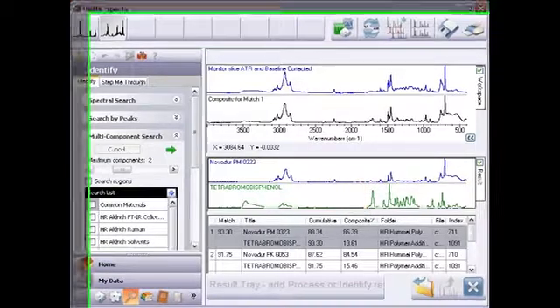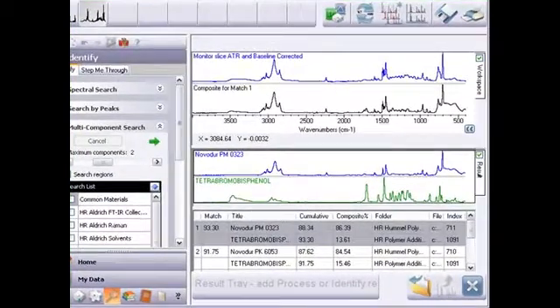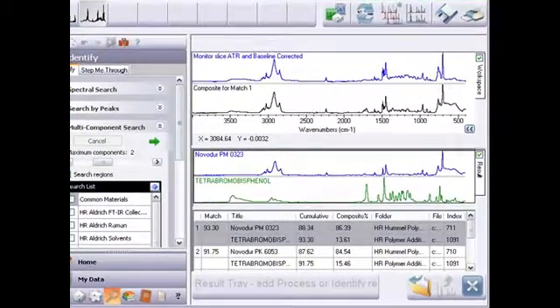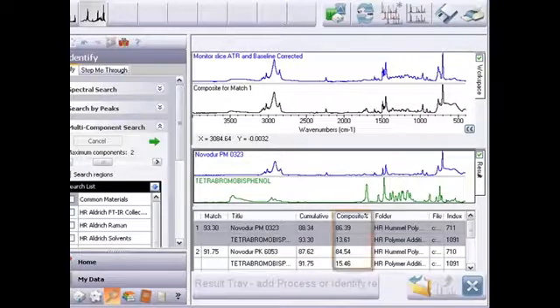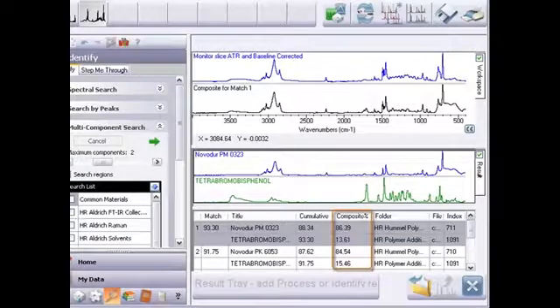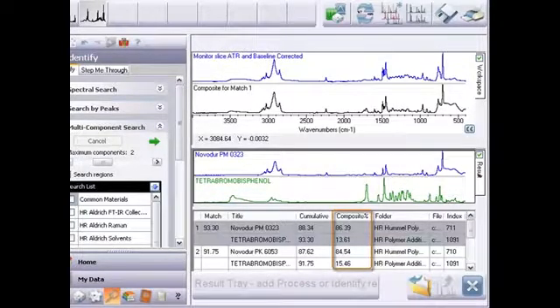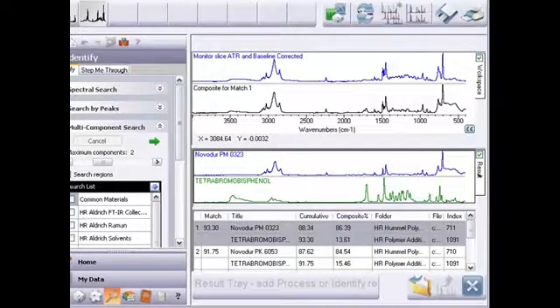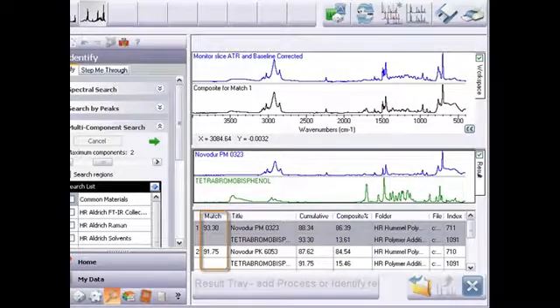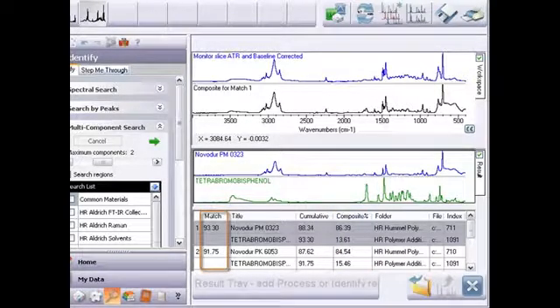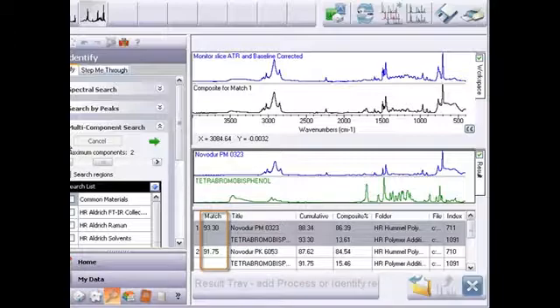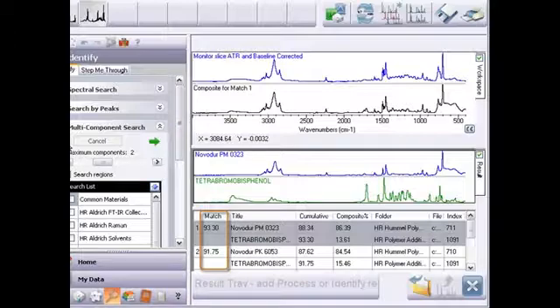Note that because library spectra are often normalized and other reference spectra may not be, the composite values are relative. Don't interpret the information quantitatively. As with any spectral search, these numbers are determined by the quality of the compared spectra, which may have been collected on different instruments with different settings. Resolution is the most important. As a result, don't expect all match values to be at or near 100.